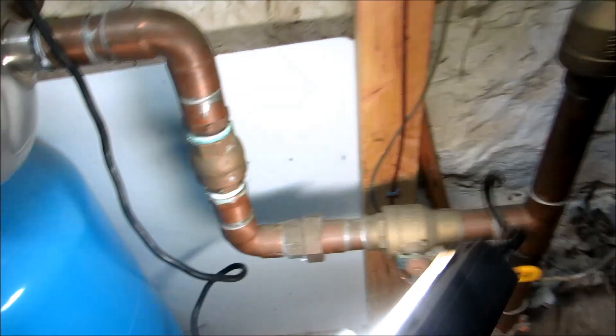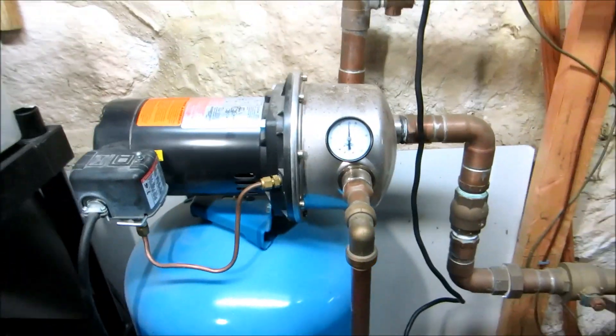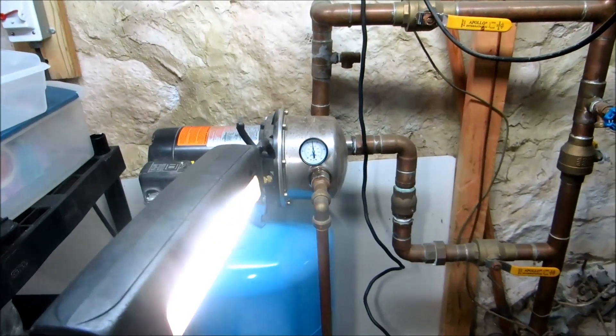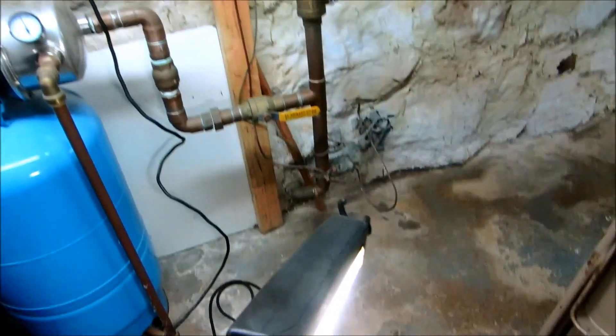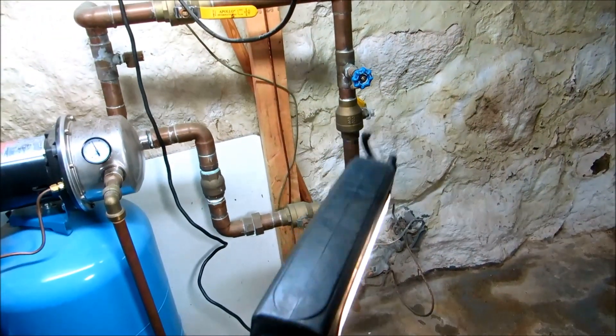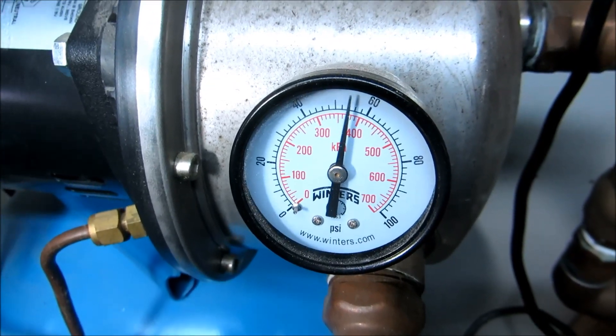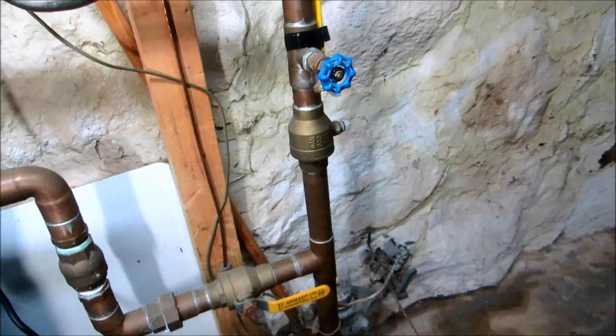There's a check valve here, so this valve has to stay closed. The complaint was that the pump was running all the time. The check valve stops the water pressure from draining back into the street. We should probably take that handle off and tape it to the pipe so they can't open it — this way nobody can open it unless they absolutely know what they're doing.